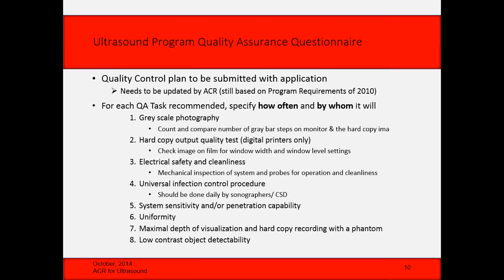So maximum depth of visualization with a phantom. So again, this is one of the ones that doesn't match. It says you don't have to have a phantom. I'm not sure how you do this test, but there are ways you could do it without a phantom, but you need some test object in order to do this. So I think that's what they meant with a test object. The vertical and horizontal distance accuracy, so commonly called geometric accuracy. So this is getting the calipers on the screen, using a phantom typically, and measuring to make sure that the pins that are supposed to be 1 centimeter apart or 2 centimeters apart are really that distance.